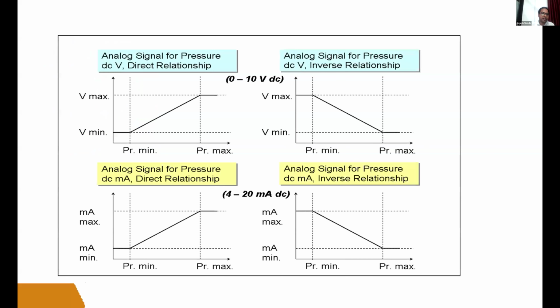In voltage output, you will get the output in the form of 0 to 10 volt DC. And if your sensor is giving the output in the form of current, you will get 0 to 20 milliamps DC or 4 to 20 milliamps DC supply. Now, in this diagram, I try to show you how exactly this pressure, temperature, or humidity data gets converted into the electrical signal.